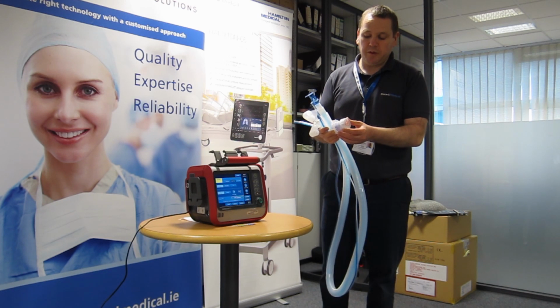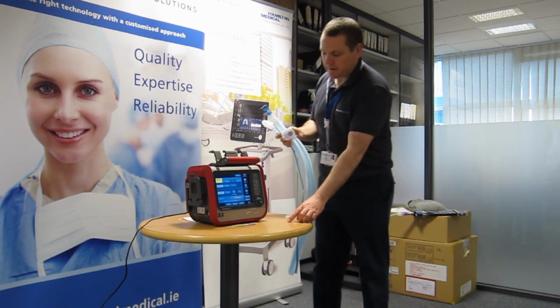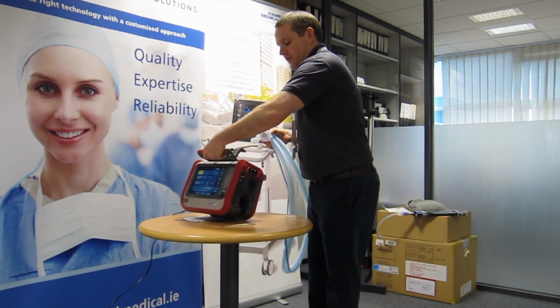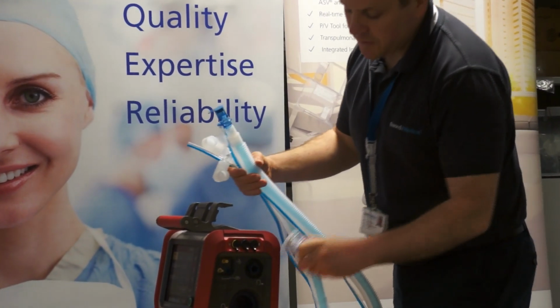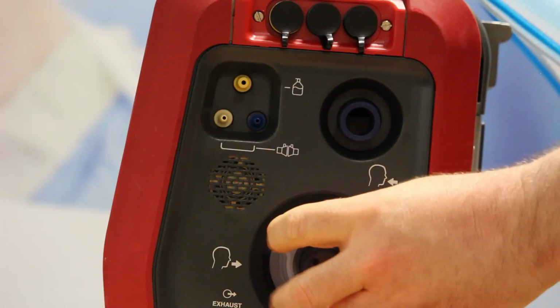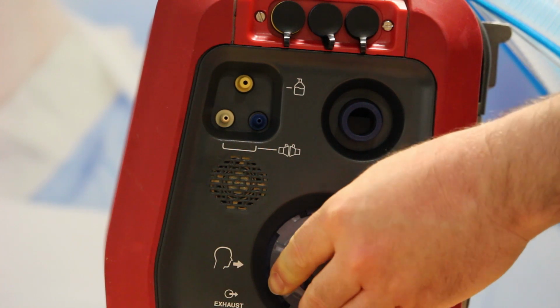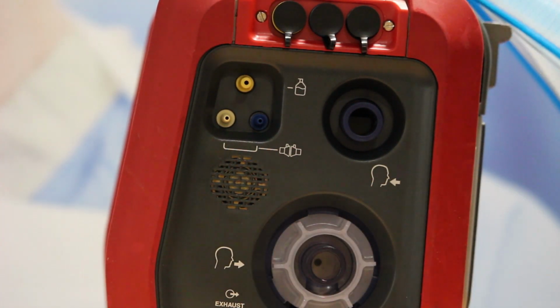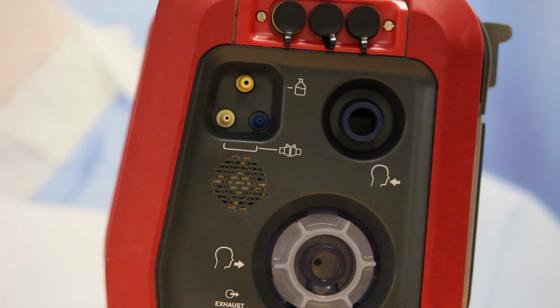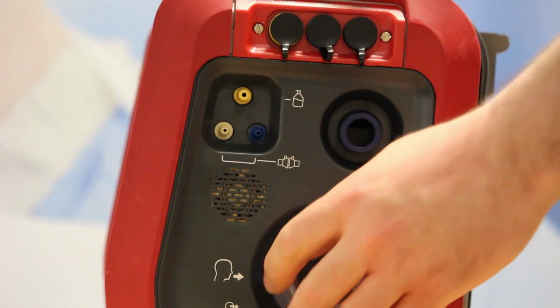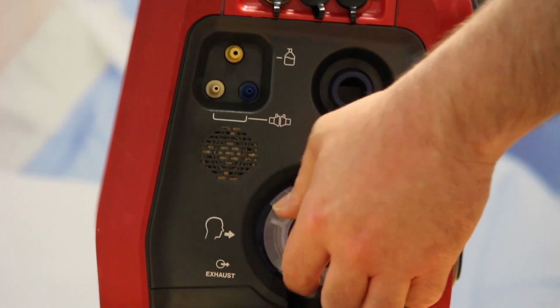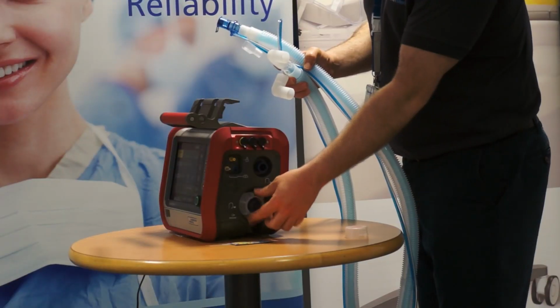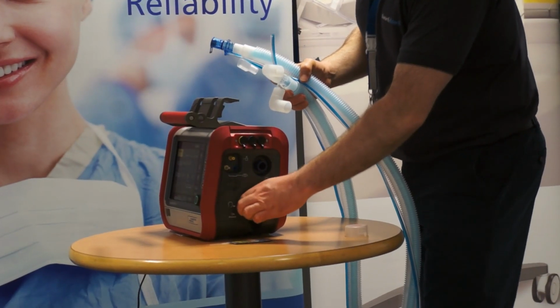It's got a removable cover to protect the membrane, and on this side of the vent is where we're going to plug it in. So the expiratory valve plugs into the expiratory port, all the way anti-clockwise to lock it in fully, and then it gets a 1/10 turn clockwise to secure it. It's one of the things to check, that if you've got a big leak, just make sure that someone has not just put that in like that, that they've actually turned it around and locked it.